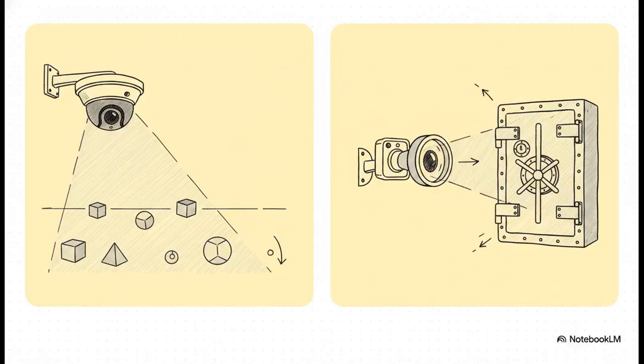To really wrap our heads around why we need a totally separate system for this, think of it like a high-end security setup. People sometimes assume ground fault protection is redundant if you've already got differential protection, since they both watch for current imbalances, but they are solving completely different problems. Differential protection is your wide-angle security camera. It monitors the whole room, tuned for balanced zone phase faults. Ground fault protection? That's your dedicated close-up camera trained directly on the safe in the corner. It zooms in on the one spot most likely to hide a small fault.